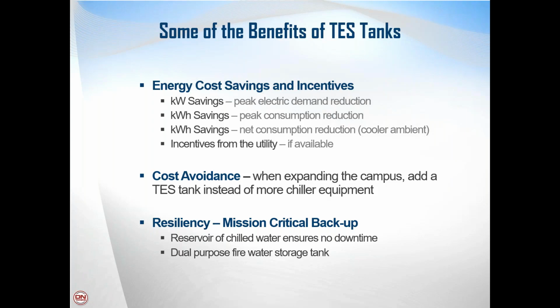Also, many times an owner is looking to replace or add a chiller to their central plant system. Perhaps they have an old chiller that needs to be replaced, or they're expanding their campus. And when they're looking at replacing or adding a chiller, that's the perfect time for them to consider, instead of adding that refrigeration equipment, perhaps I should add a thermal storage tank. We're going to look at an example of that later in this presentation, and it's a very economically beneficial way to consider adding a tank to a system.